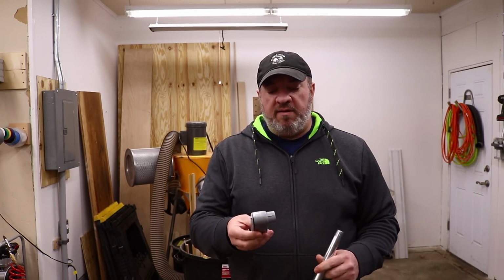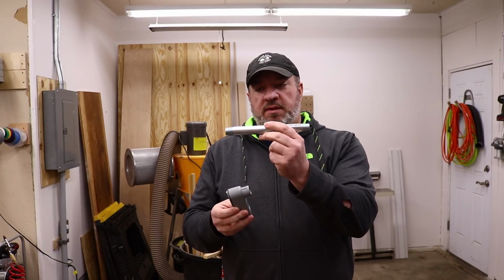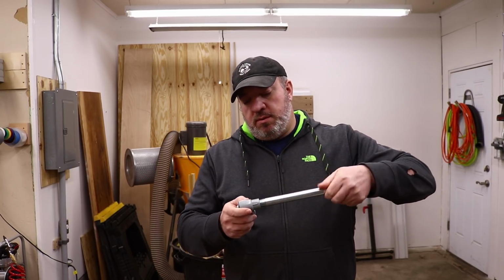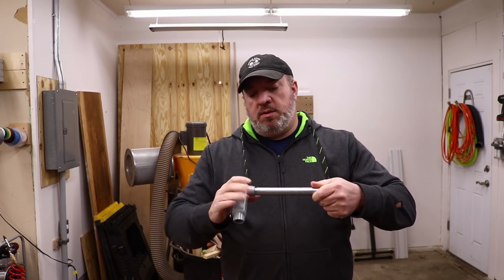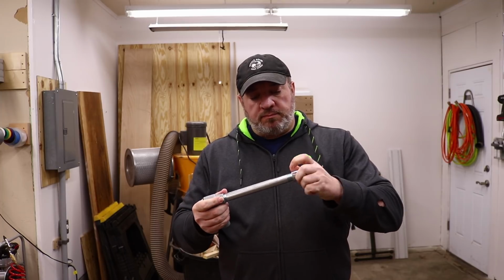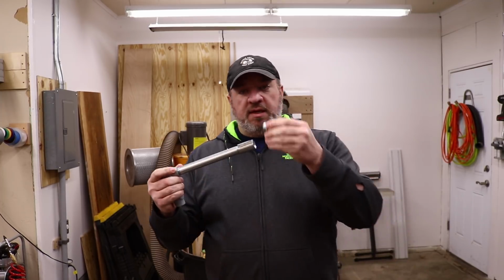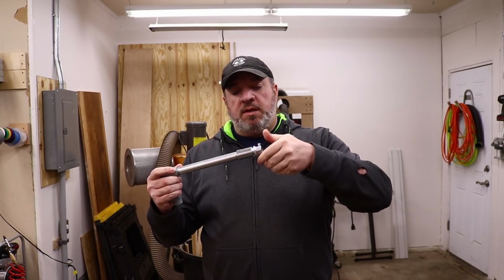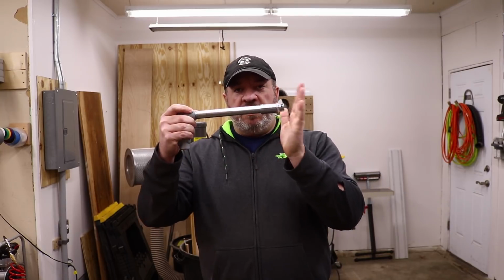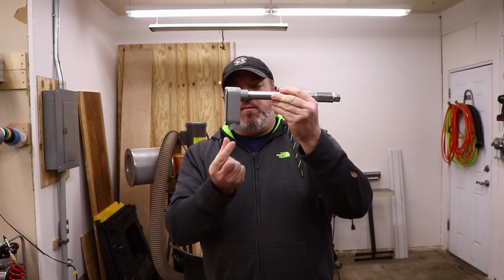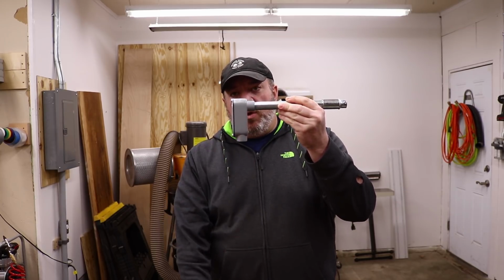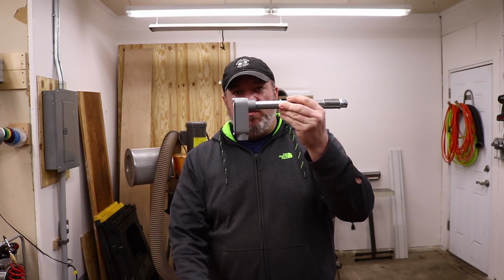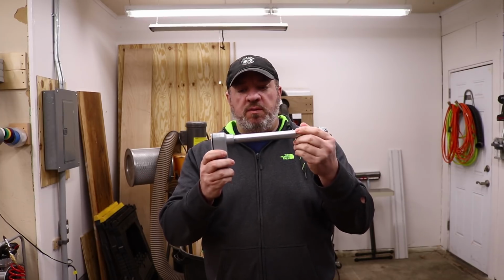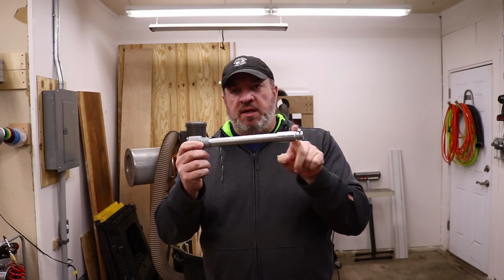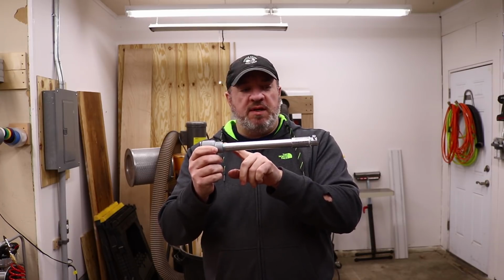Where it goes to the wall, we have a galvanized L, which screws into this galvanized nipple, like so, and then has this galvanized connector, screws on like this, and then I can take a regular EMT connector, screw that in. So this will be on the inside of the house, this will be on the outside of the house. And I'll have rain tight fittings that go into here, more EMT going down to the disconnect where another rain tight fitting will fit on that disconnect. The reason I'm doing this is because all this right here is rain tight. And it needs to be because it's going to be outside and exposed to the elements.